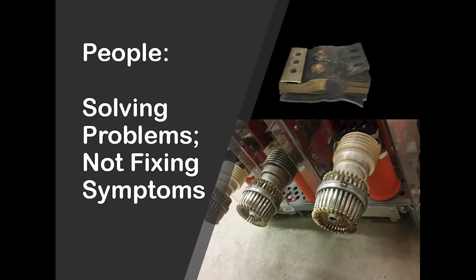Another electrical testing company failed this circuit breaker. You can probably notice the B-phase pole is discolored from a lot of heat generated by a bad connection. That company said it's a bad vacuum bottle and you'd need to replace the entire pole assembly with a new bottle — a pretty expensive repair, truthfully.